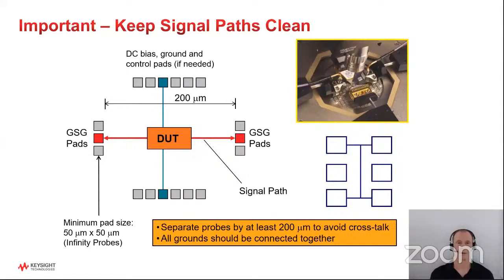Another thing to keep in mind if you're making high-speed measurements is that you want to keep the signal paths clean. So if you do have some sort of control signals going to your DUT, you want to keep those perpendicular, as shown here, to the signal path. You want to keep the signal path flowing straight, not having any of these control signals in the way, and put any other control or biasing signals like that going perpendicular to it. The picture in the upper right of this slide shows how you would do that on an actual wafer. Also try to keep the probes separated to eliminate crosstalk, and make sure all grounds are connected together so that you have a nice solid grounding when you're making these high-speed measurements.